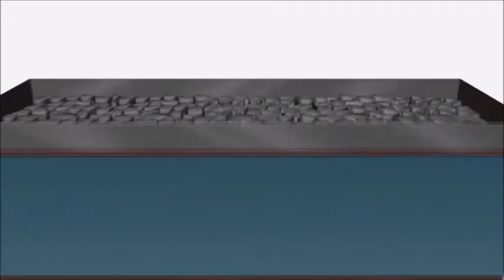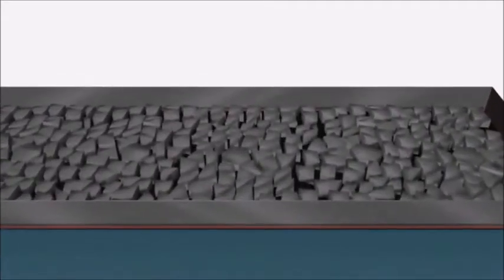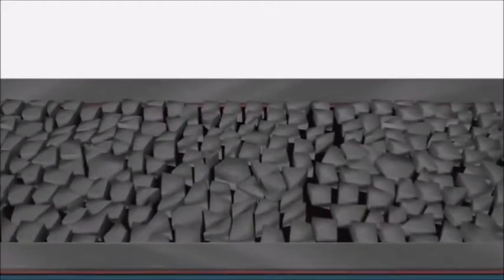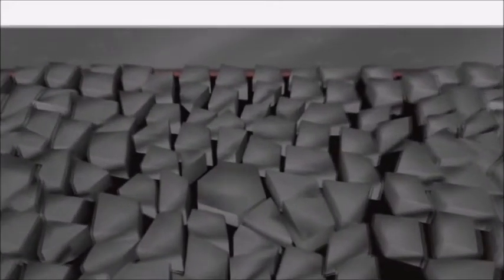This video provides an introduction to radiographic film processing. The first step in the generation of an X-ray image is the creation of a latent image. The latent image is created through the interaction of silver and halide atoms within the X-ray film.